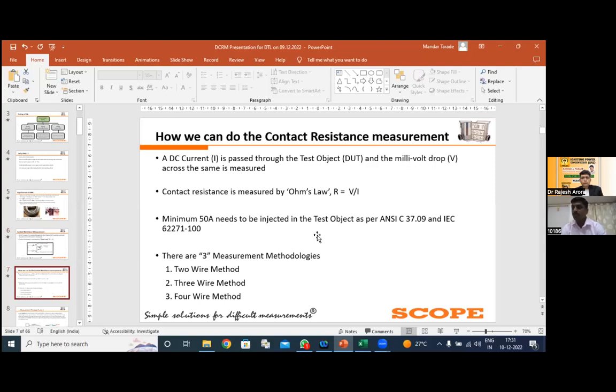But please remember that we are performing the entire testing in a live switchyard, which is surrounded by induction. Whenever we connect the cable to our DUT, which is almost 14 meters above the ground potential, the cable gets charged.